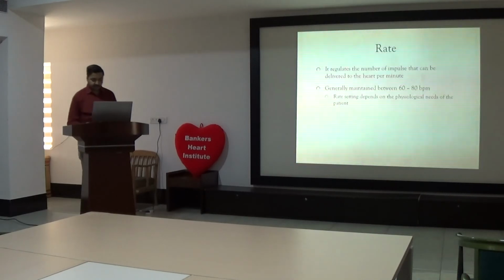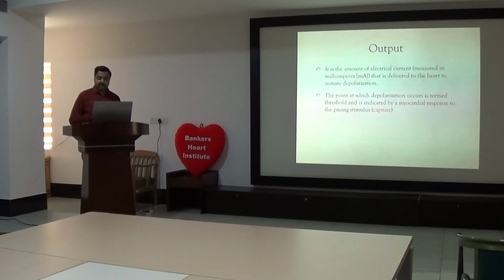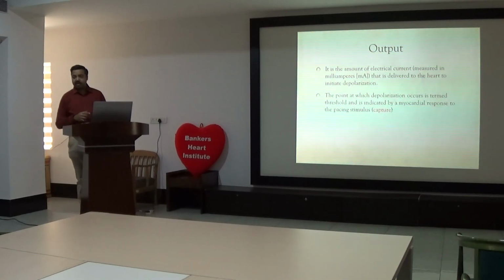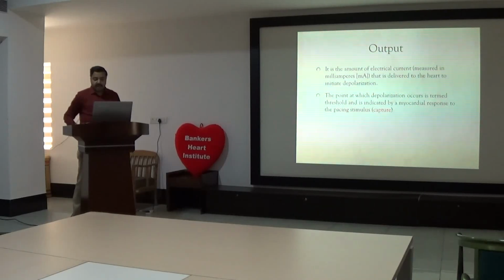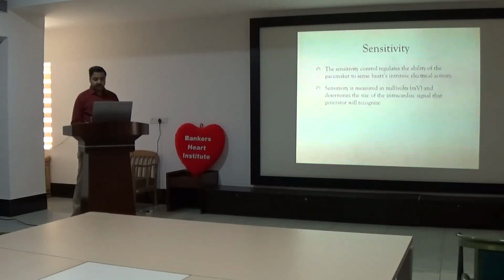So rate is the number of impulses that can be delivered to the heart per minute. Generally it is kept between 60 to 80, but depending on physiological rate it can vary. Output is the amount of electrical current that is delivered to the heart to initiate depolarization. And the point at which depolarization occurs is termed threshold and is indicated by myocardial response to the pacing stimulus. That is, in a permanent pacemaker, this terminology is called capture. Sensitivity controls and regulates the ability of the pacemaker to sense the heart's intrinsic electric activity, and it is measured in millivolts.